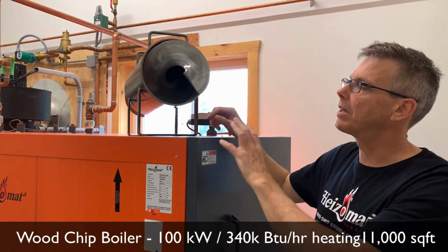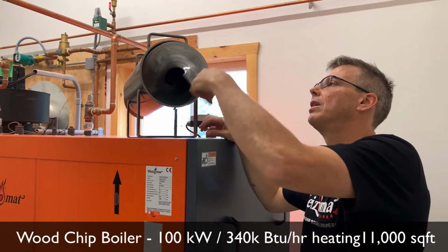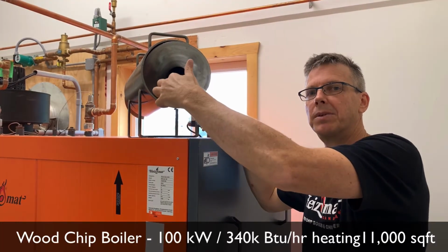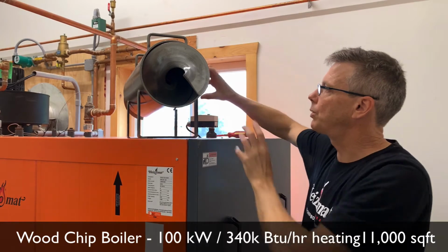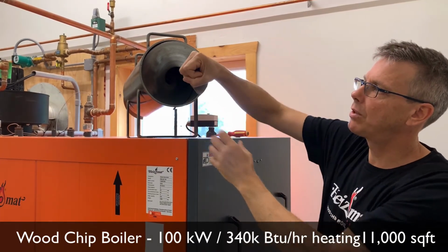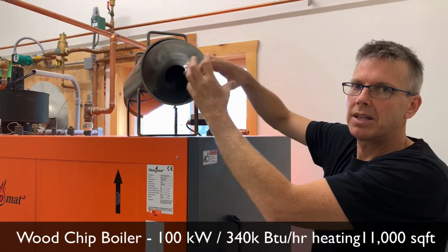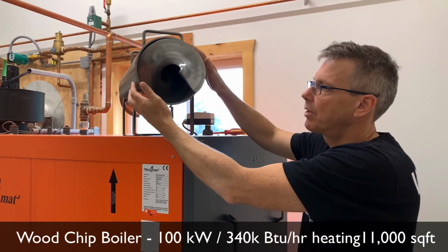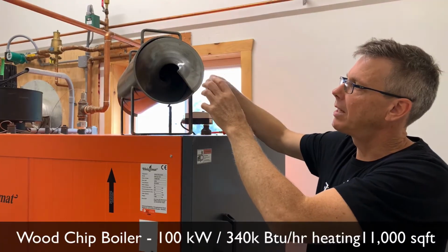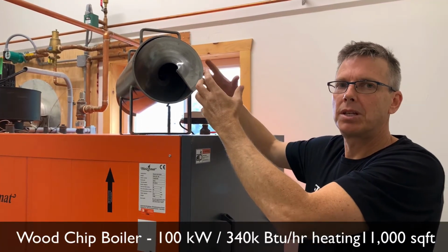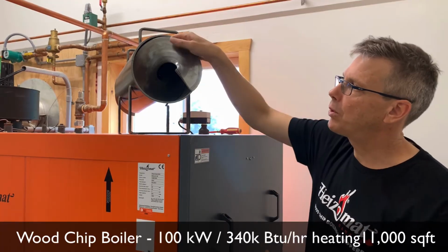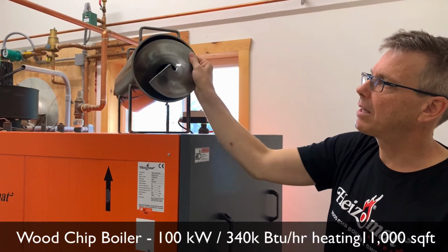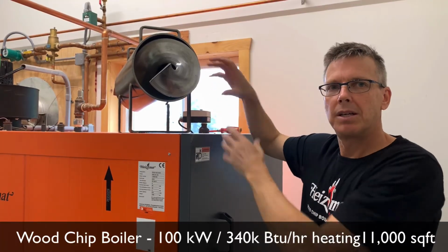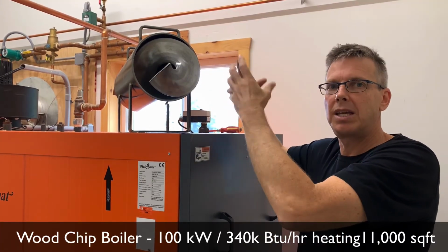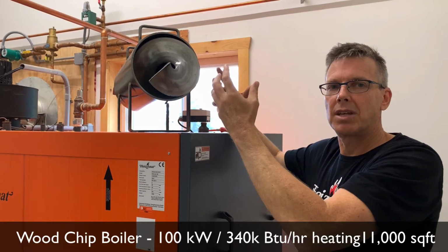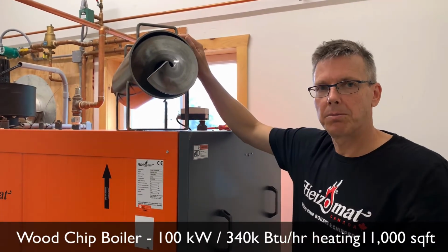So when the auger is not moving, what's interesting is that it actually causes the hot gases to rotate or spin. And so rather than the hot air just shooting straight down the tube, which means that the center of the air would be hot and the outside would be cooled by the heat exchanger in contact with the water, by rotating it we create turbulence, which actually improves the efficiency of the heat exchange. When they turn, they actually scrape the sides of the tube to make sure that we keep those tubes clean, which again keeps the efficiency of the boiler high and saves you ever having to go in and brush those tubes out.